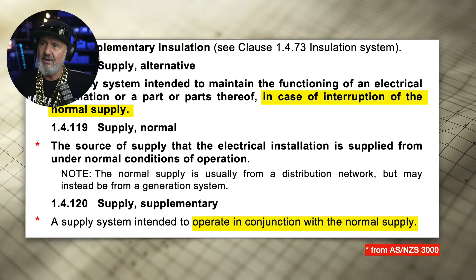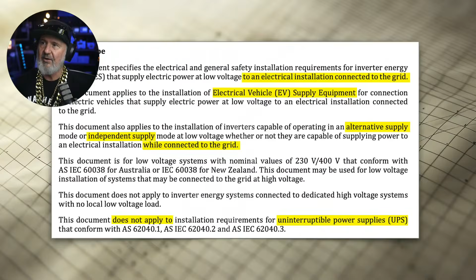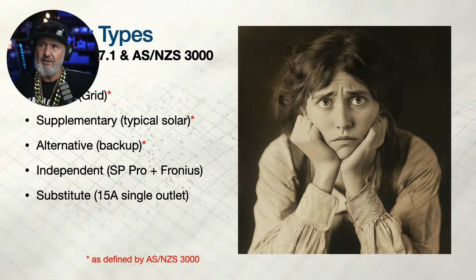Alternative supply is one which can be an alternative to the grid, such that in case of interruption of the normal supply, it can maintain the functionality of that electrical installation. Let me skip back a couple of slides to show you those again. An alternative supply is what you would think of as a normal backup circuit on a hybrid inverter, so it can provide power to the backup circuit, whereas an independent supply can completely function, such as having an SP Pro and Fronius in combination. I gave that as an example, where when the grid's not available, the SP Pro becomes a grid-forming inverter system and allows the Fronius inverter to parallel with it and continue to provide a source of energy. That's an independent supply. So yeah, those definitions, alternative and independent, are a little bit tricky.